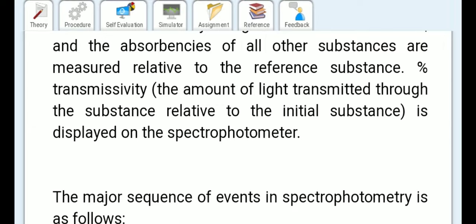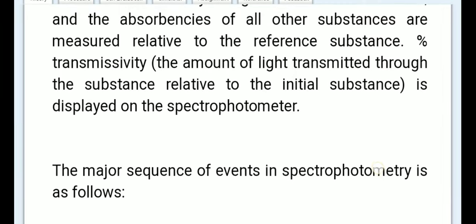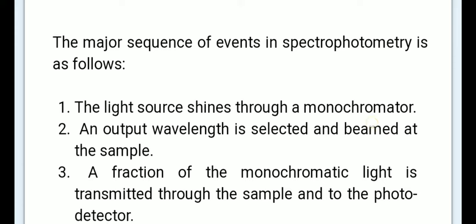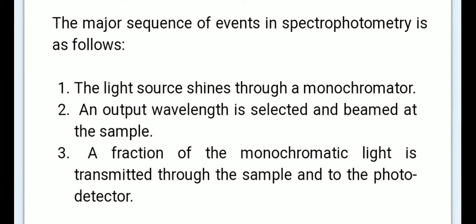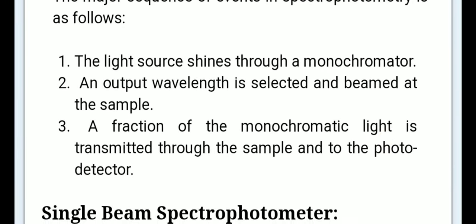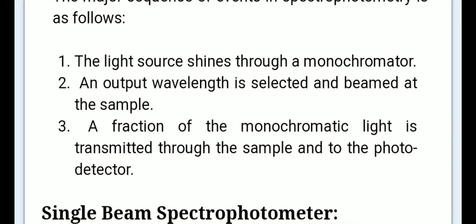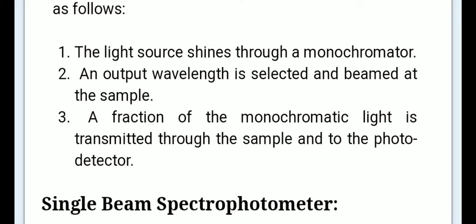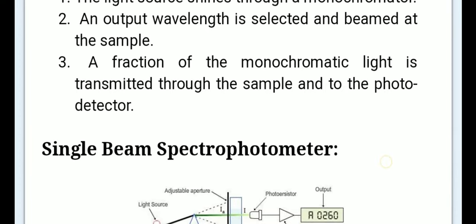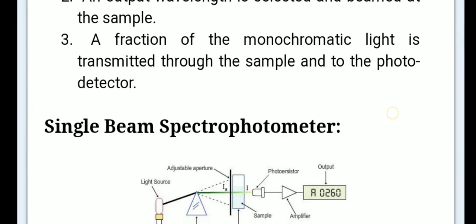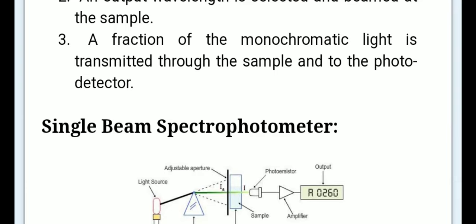The percentage transmittance — the amount of light transmitted through the substance relative to the initial source — is displayed on the spectrophotometer. The major sequence of events in spectrophotometry are: first, the light source shines through a monochromator; second, an output wavelength is selected and beamed at the sample; third, a fraction of monochromatic light is transmitted through the sample to the photodetector.